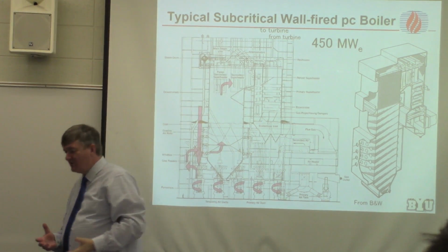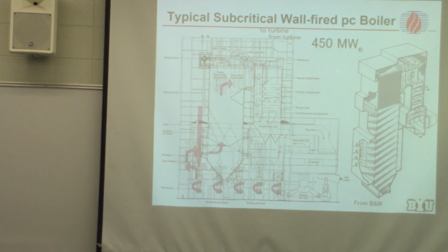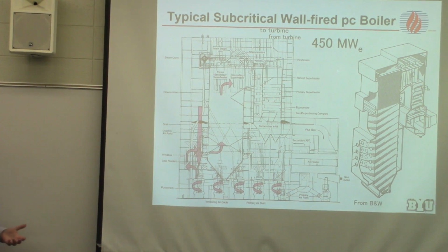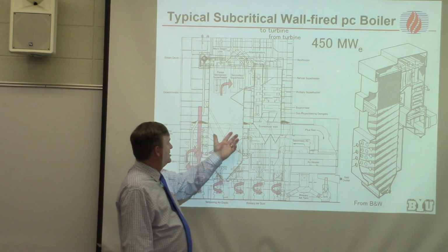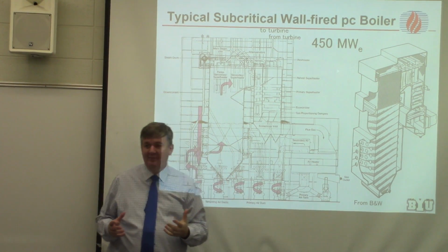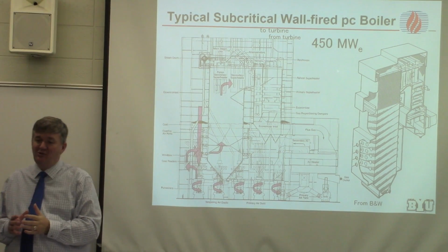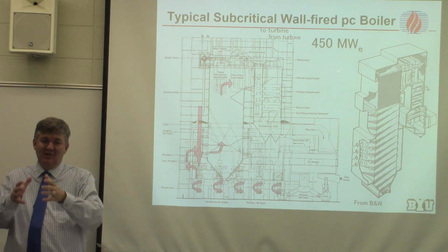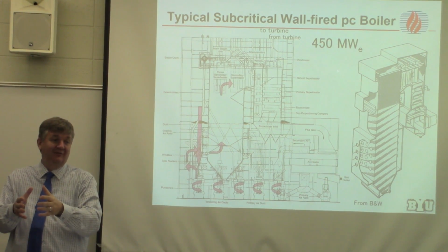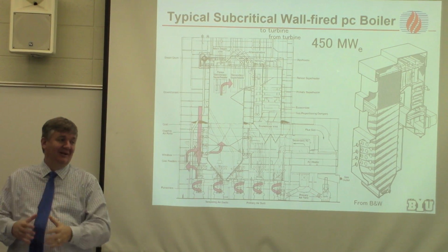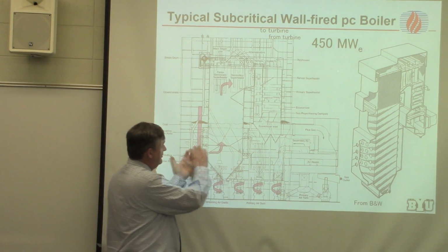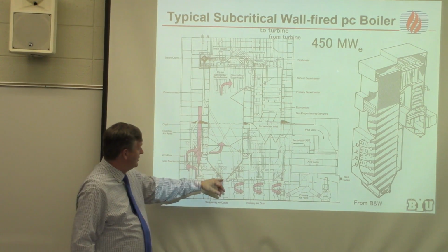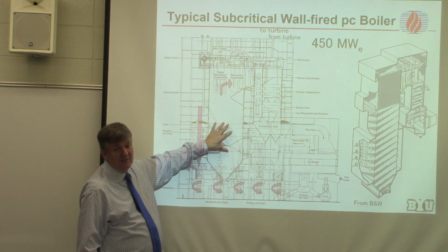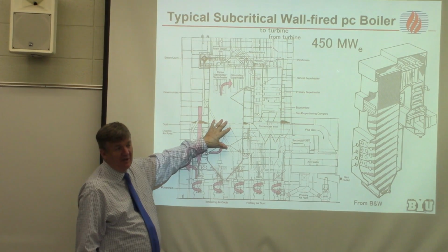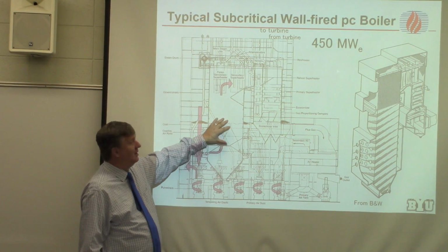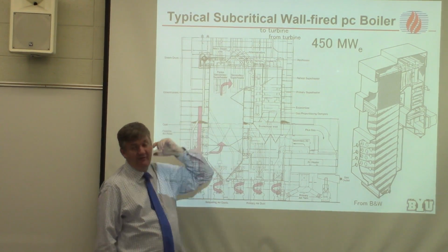And the flame is so intense. Remember we talked about these 2,000-and-some-degree temperatures, there's actually nothing that you can put in this fireball that would have any lifetime of any significance. So what you're trying to do is get heat out of this flame, but you can't put heat exchangers and stuff like that into the flame because it would just destroy them. And so the walls of this boiler have water going through pipes in them, absorbing the heat almost entirely by radiation from that fireball, at least up until this point of the flame.